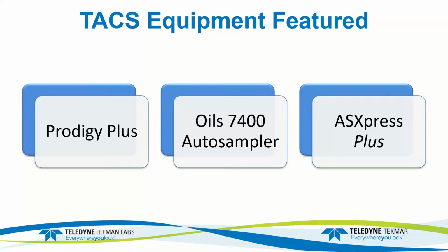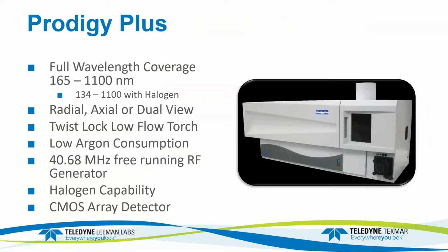to the data collection. So just to introduce the Prodigy Plus, it's an optical system that can cover from 165 up to 1100 nanometers. It's available as an axial, radial, or dual view system. In this particular application, and for oils in general, we recommend the radial view. It has a low flow torch, low flow argon consumption, and free running generators. One feature of the Prodigy Plus is its halogen capability, which sets it apart from most other ICPs, and it also uses a CMOS array detector, which is the modern detector.